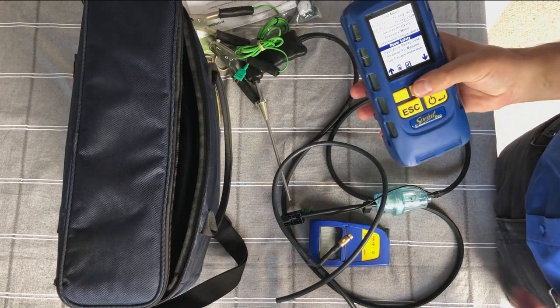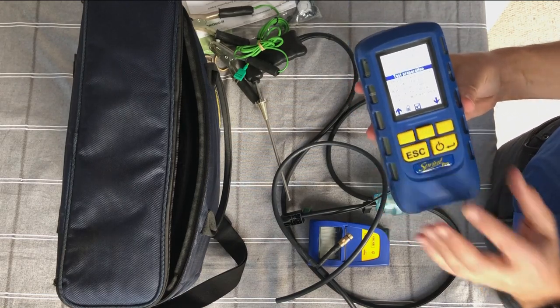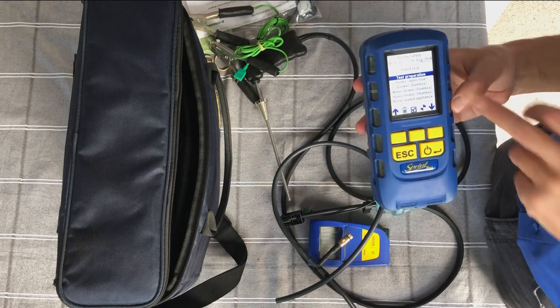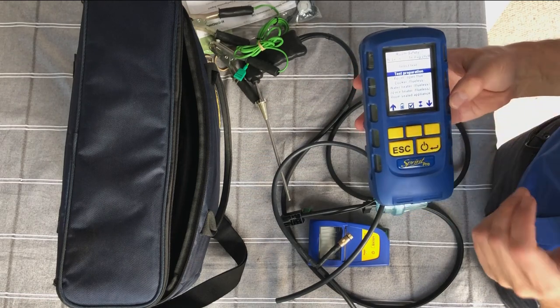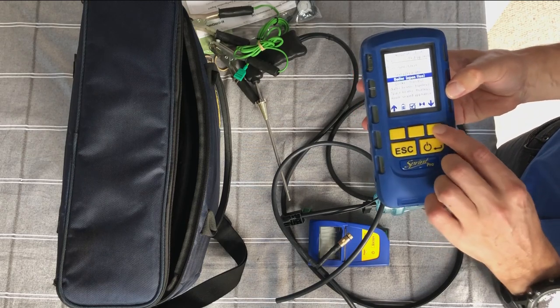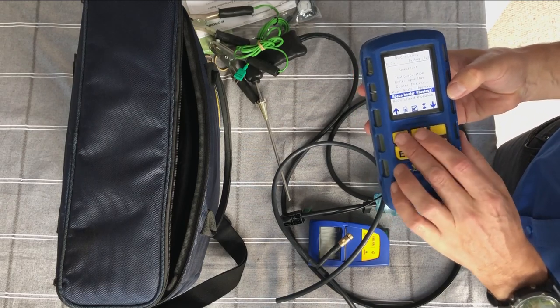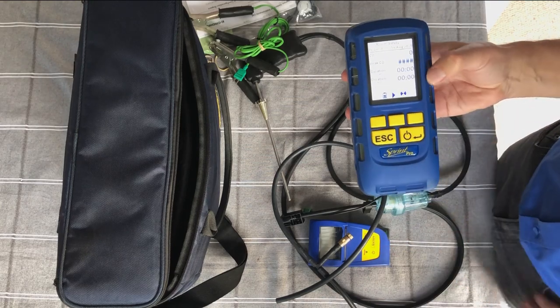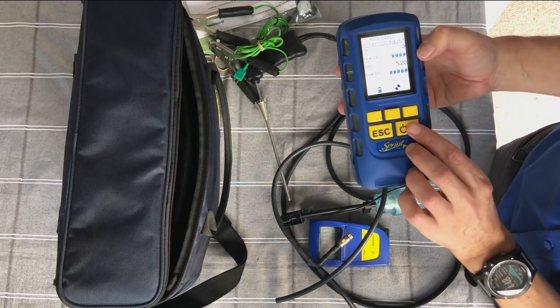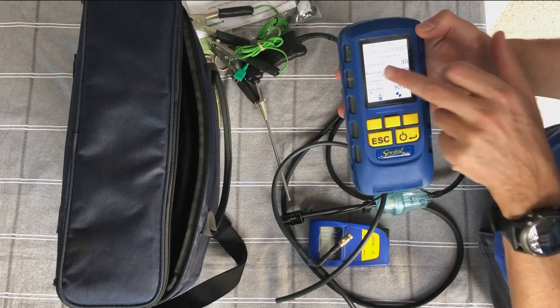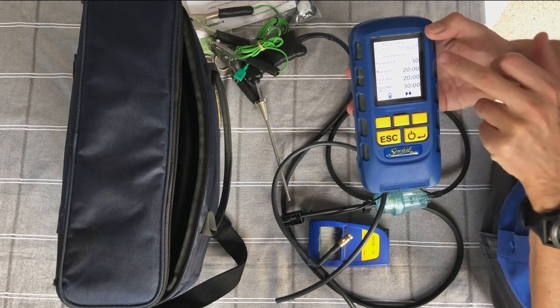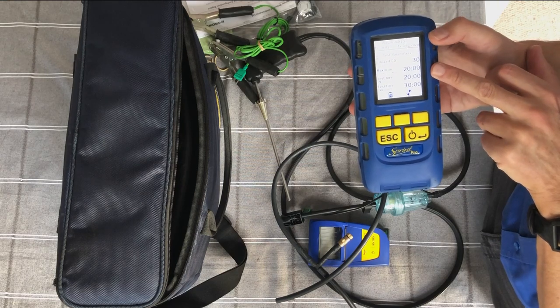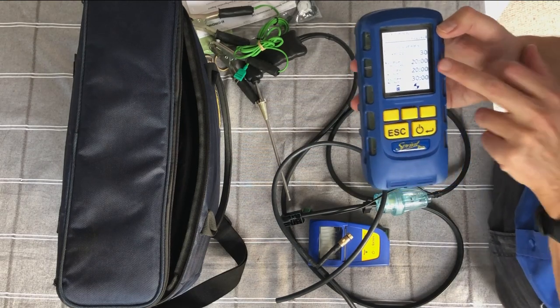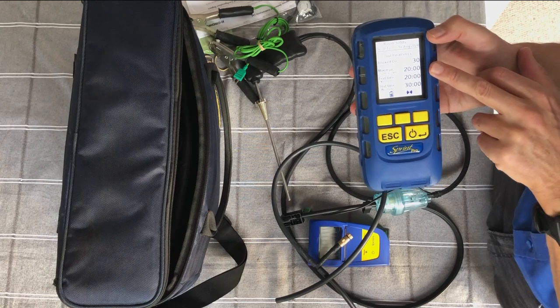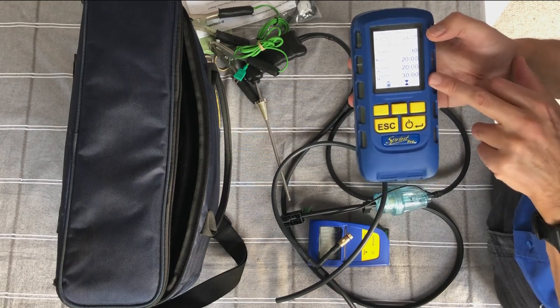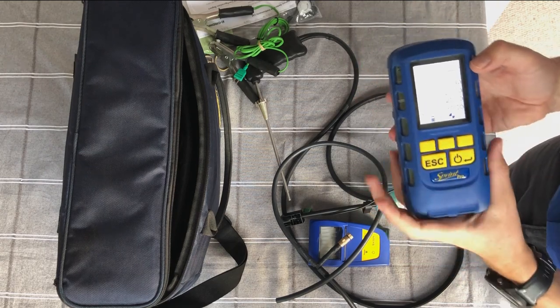If I go into room safety, it's going to bring the pump on again, because it's basically a function of flue gas analysis. So with ours, if you know you're going to be testing, say, a CO room test for a cooker, you go in, you choose cooker. So again, you use these buttons up and down to choose the one you want. Choose cooker, and if I go through the pages, it actually tells you the test parameters. So it's an allowed parts per million of 30 ppm. You're allowed 20 minutes above that 30 ppm, and the test time minimum is 20 minutes, and the test time maximum is 30 minutes. So it tells you the test parameters.